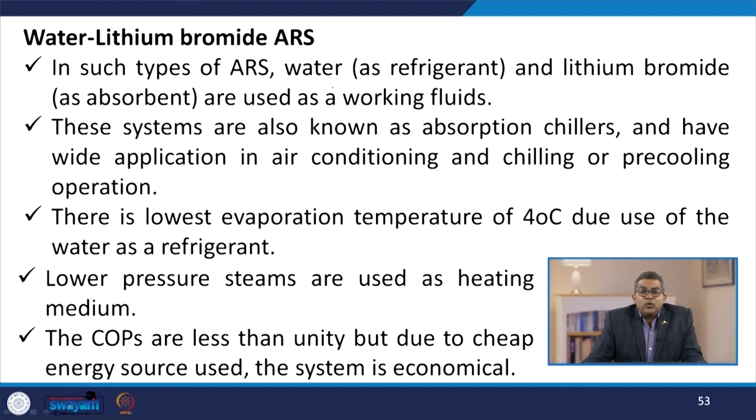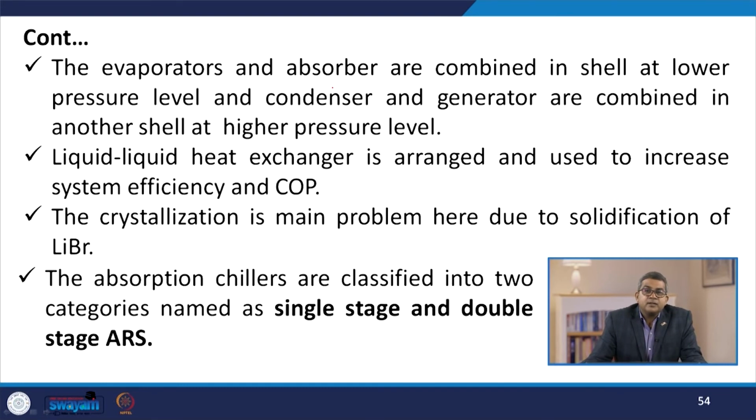Now, there is lowest evaporation temperature of say 4 degrees Celsius due to use of the water as refrigerant. Lower pressure steams are used as a heating media. The coefficient of performance is less than unity, but due to cheap energy source used, the system is economical.